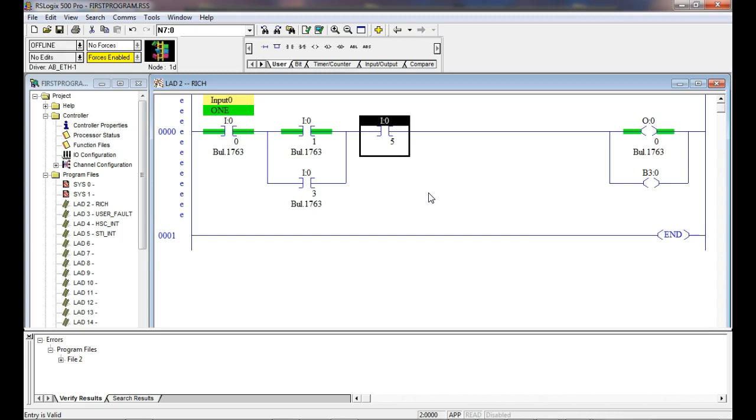So I could have a position sensor hooked up. The PLC doesn't know what's giving it a 1 and what's giving it a 0. All it does is say, okay, it's either true or false. So all those sensors over there, you notice when I triggered them with my hand, it just turned the light on in front of the PLC, which says, okay, I'm getting 24 volts back from whatever that is, right?